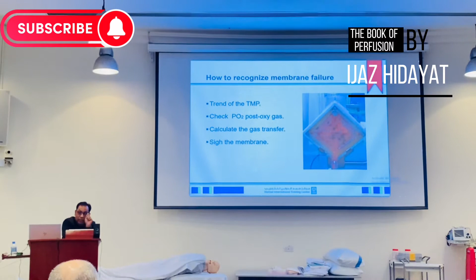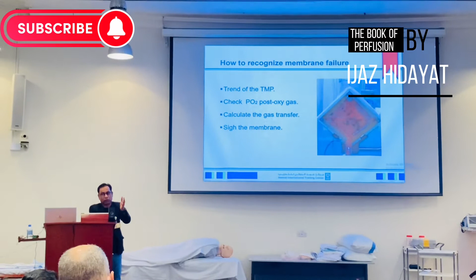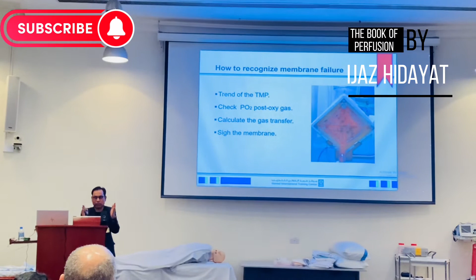And then you have to do the sigh. You increase the sweep gas flow so that the gas flow pushes all the water out of the oxygenator, and your membrane will be free from the water, and then you will find the color change in your tubing.